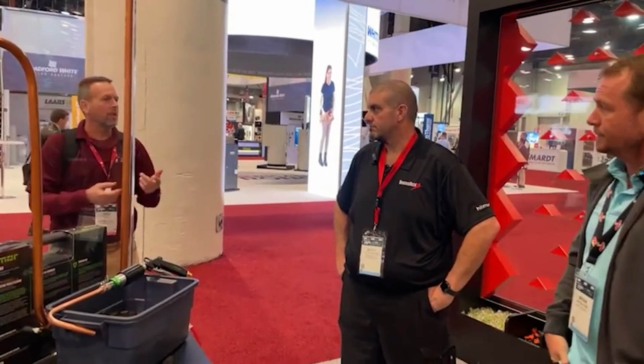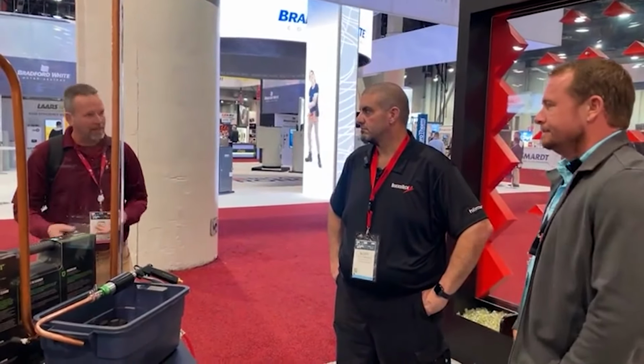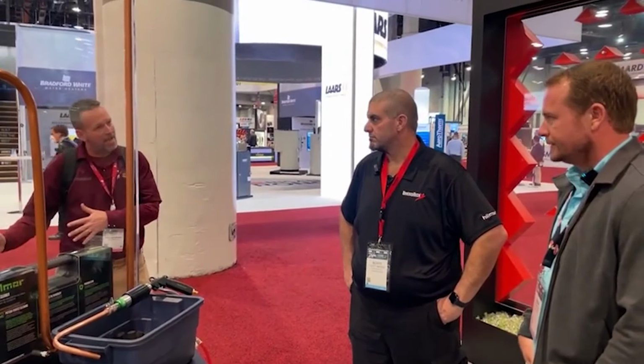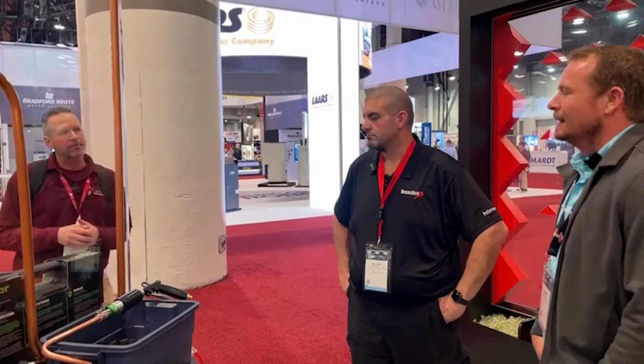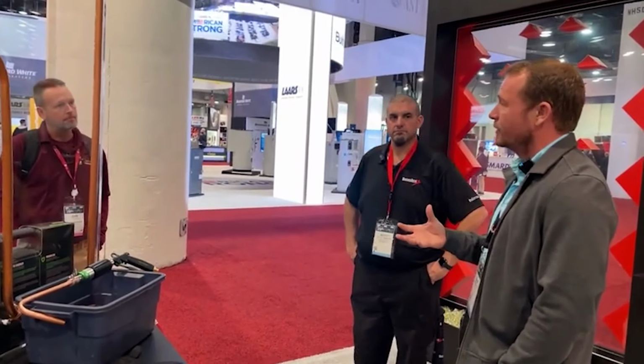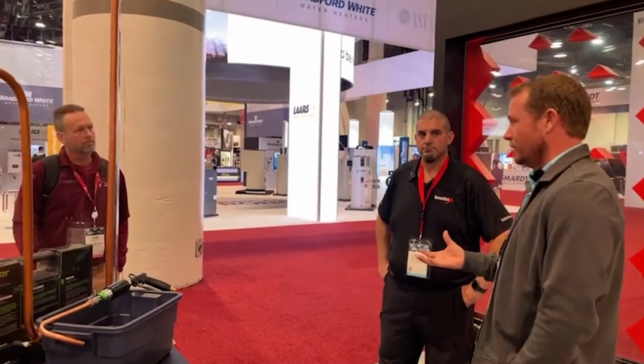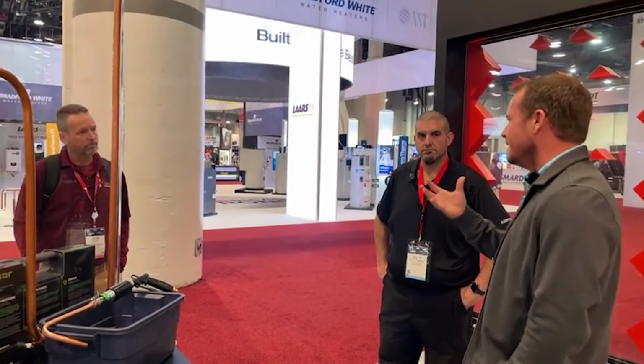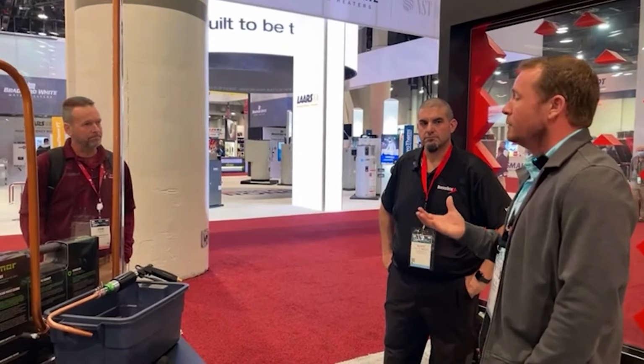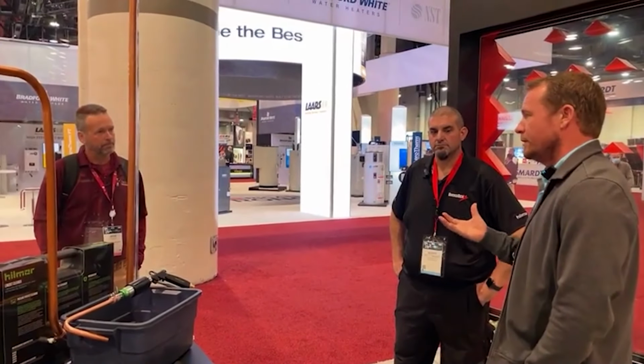We talked about that in your class, like you've got to put the burnout kit and all that stuff in, then theoretically come back, pull that out, and put a new dryer on there. Will this eliminate any of those steps? It's not going to eliminate those steps, because most of your oil charge is contained in the compressor and the accumulator, and a lot of it's also in the condenser coil. So this isn't going to eliminate the need to do the acid protocol, but it would be a nice step, especially in a pretty extreme circumstance.